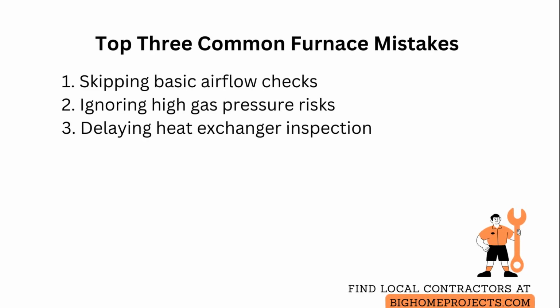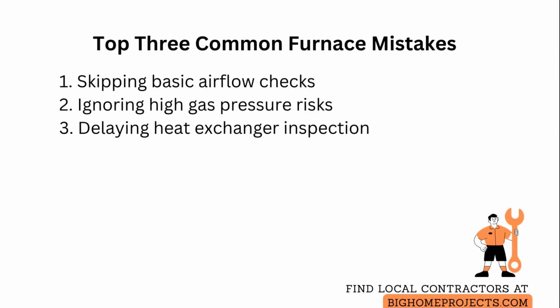A third common mistake is delaying heat exchanger inspection because it is costly, but letting cracks worsen risks safety and repeated trips, so arrange prompt inspection and repair when any signs of stress appear.